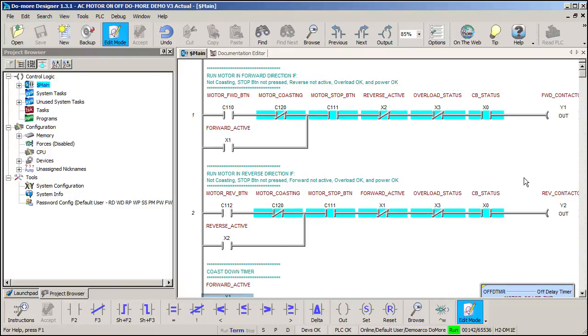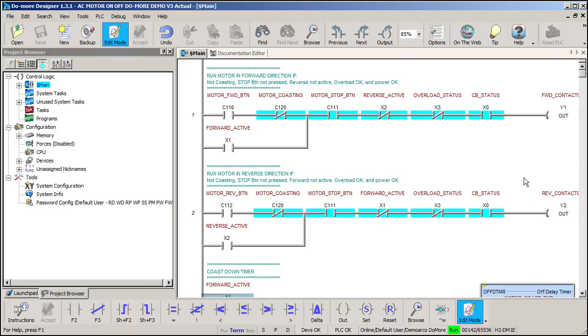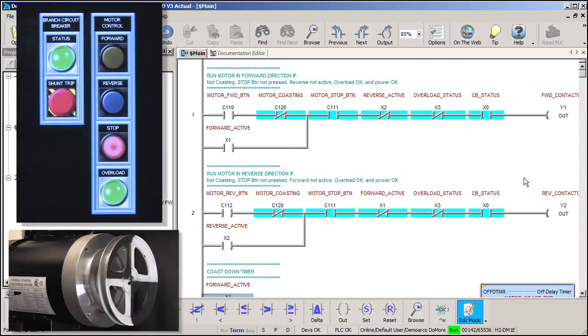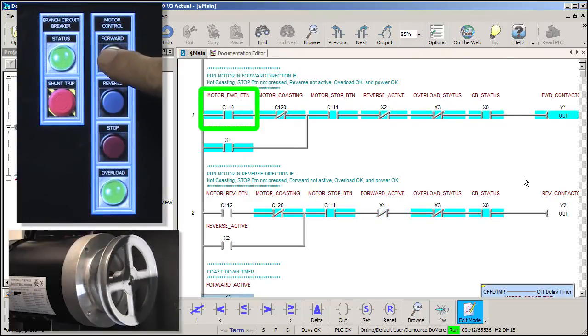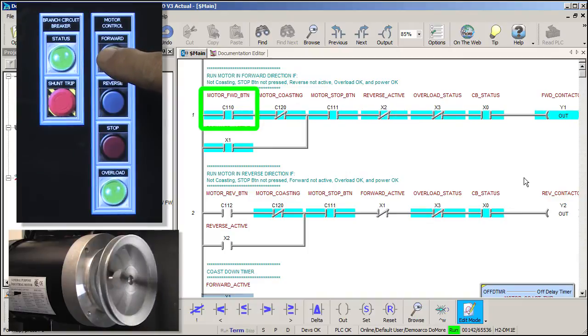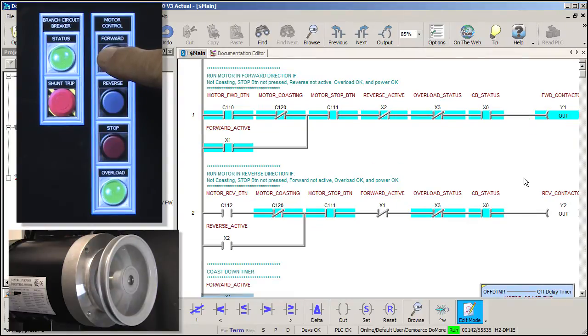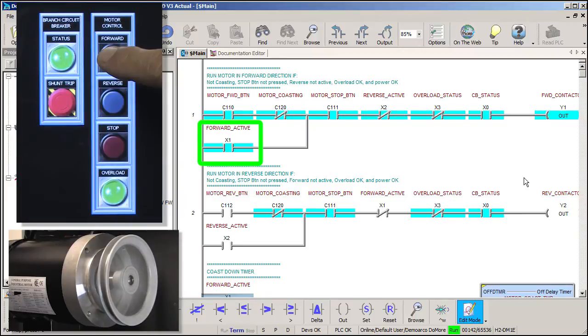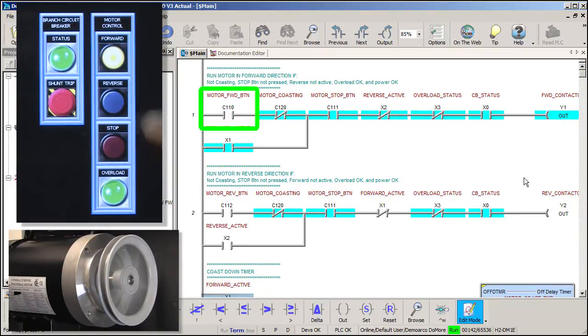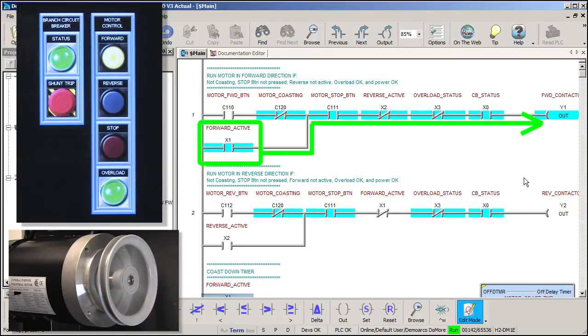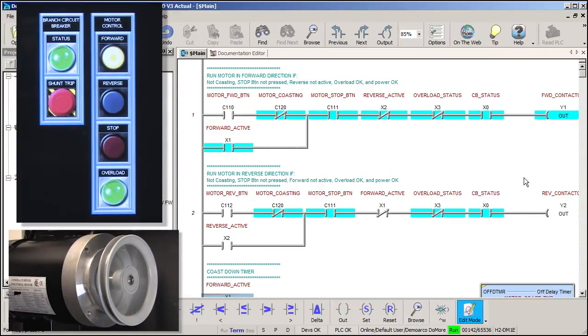If we press the overload test button, we see that go inactive and if we flip the motor circuit breaker off, we see its aux contact open up. Great, looks like things are working. So, when we press the forward button, we now have all the contacts on this rung active and power flows to the output coil and starts the motor spinning. Once the contactor engages, its aux contact will also engage, which is this contact right here. So when we release the momentary forward button, this aux contact will keep the motor running. We call that sealing or latching the circuit.